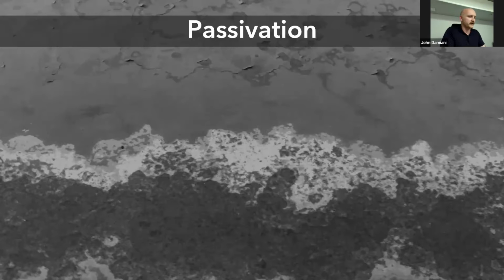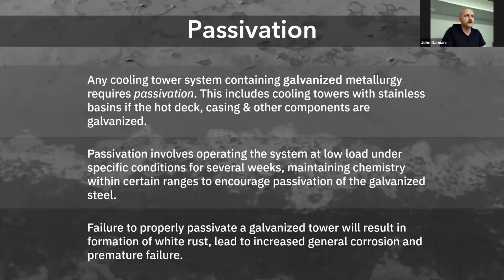Okay, we'll talk about passivation quickly. Basically, any cooling tower system with galvanized metallurgy requires passivation, so when you have a new system, this is really important. That includes stainless basins, as I mentioned; if the casing and the hot deck are galvanized, you still need to do it.